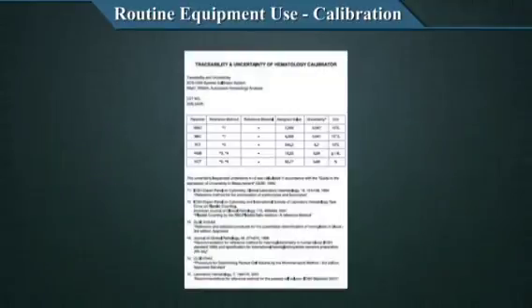Okay, so I'm going to show you a calibrator insert for an analyte calibration. In this case, a hematology calibrator for a cell counter. The product insert is titled the traceability and uncertainty of hematology calibrator. If you look at this sheet, you will see there are multiple columns. The first column is the names of your analytes, WBC, RBC, platelets, etc. Moving on to your fourth column, you see your target values. And in the next column, the fifth column, you see the uncertainty of each component.